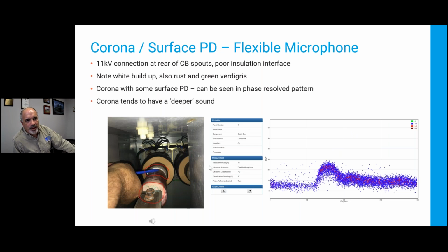So here's an example where we're getting corona and surface discharge. Now corona, because of the nature of how electrons want to move, occurs more on one polarity versus the other. And that's why we see a bigger point here, but only one. And so what we get is a more 60 hertz undertone and a very characteristic waveform. So we can tell that we've got corona discharge, not surface. Now in this case, they had both. They had to clean up the corona, and then once they did, they could see that they had surface discharge as well. So that's why we want to know that we've got corona, so we can get rid of it and keep it from preventing us from seeing that we had surface discharge as well.